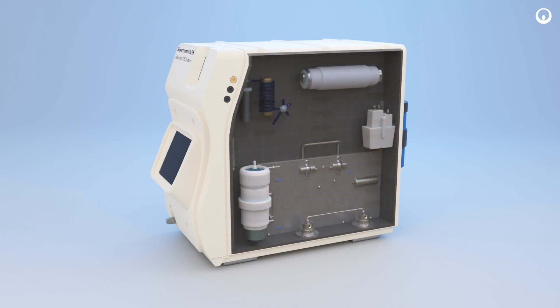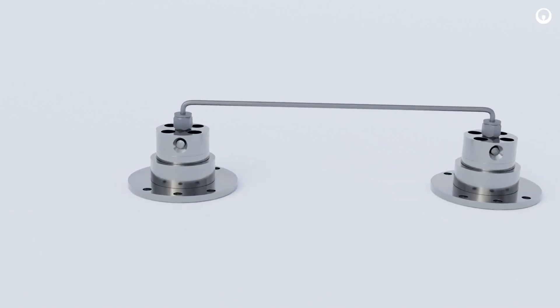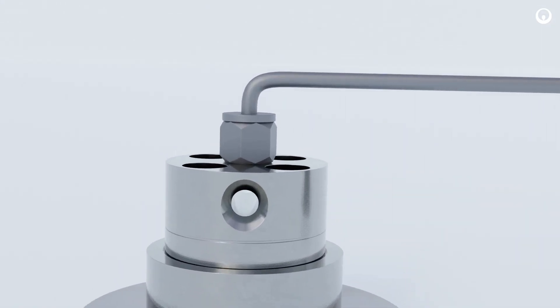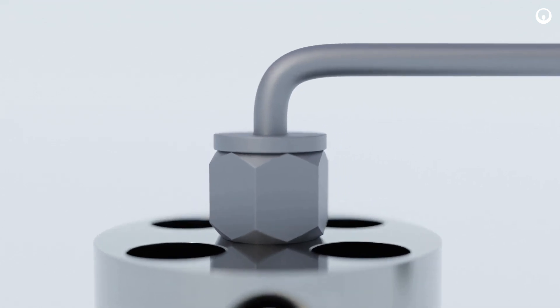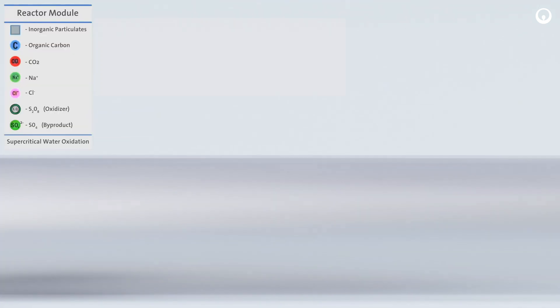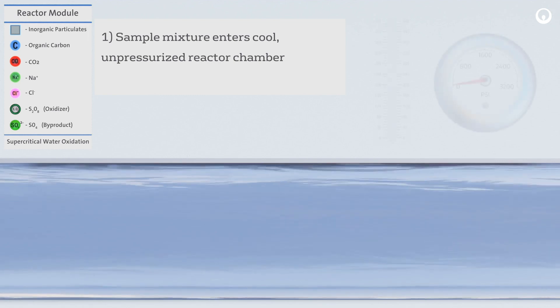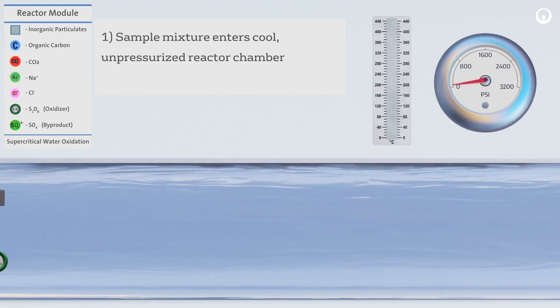Supercritical water oxidation technique occurs in the reactor module of the analyzer. Let's take a deeper look at what is happening to the sample in the reactor chamber. First, the sample enters the cool, unpressurized chamber.